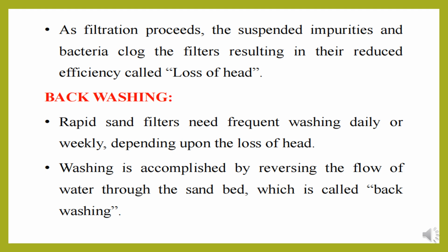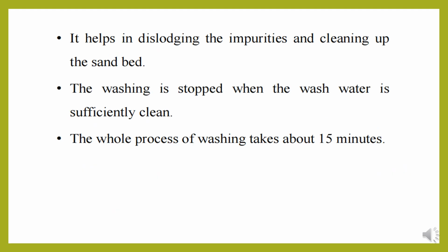Now coming to backwashing. Rapid sand filters need frequent washing, daily or weekly, depending upon the loss of head. Washing is accomplished by reversing the flow of water through the sand bed, which is called backwashing. It helps in dislodging the impurities and cleaning up the sand bed. The washing is stopped when the wash water is sufficiently clean. The whole process of washing takes about 15 minutes.